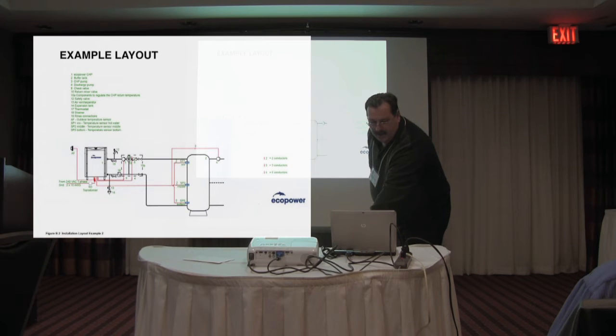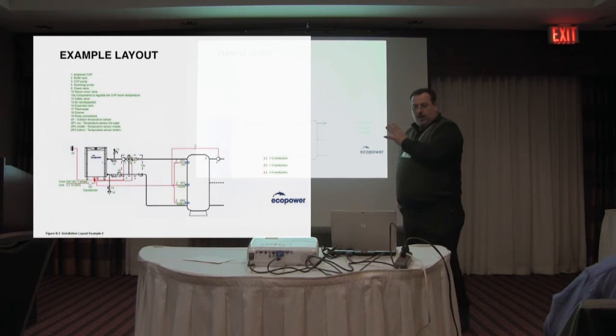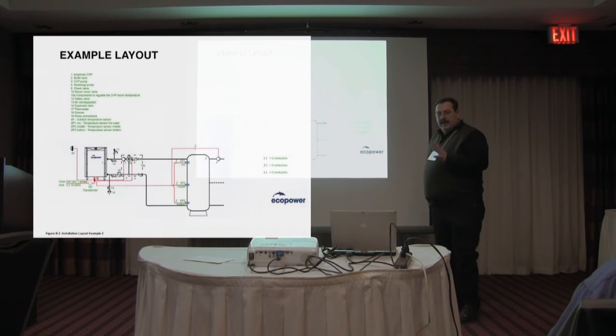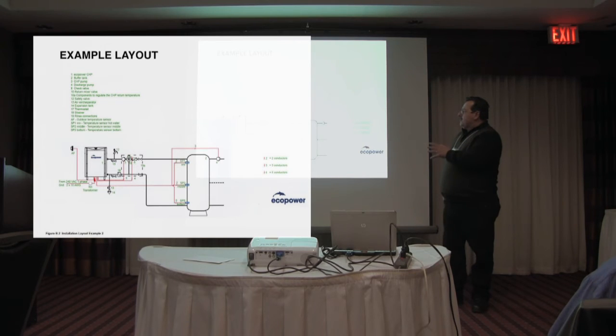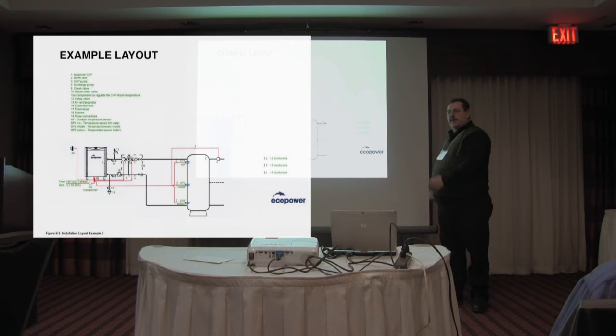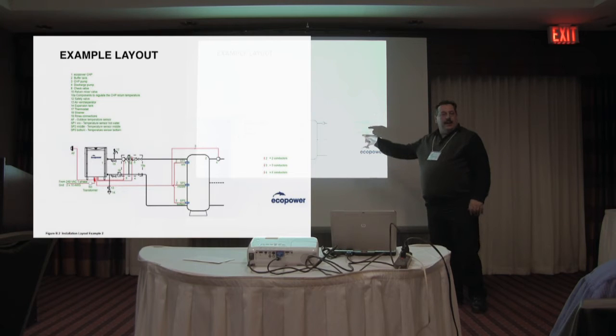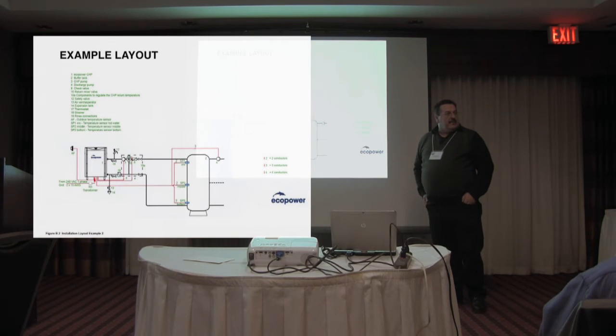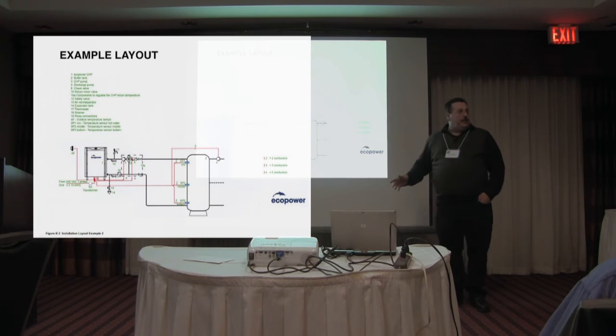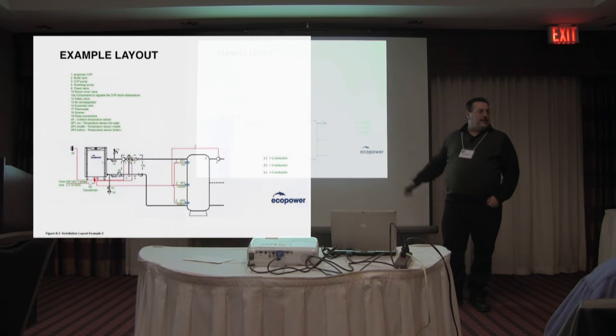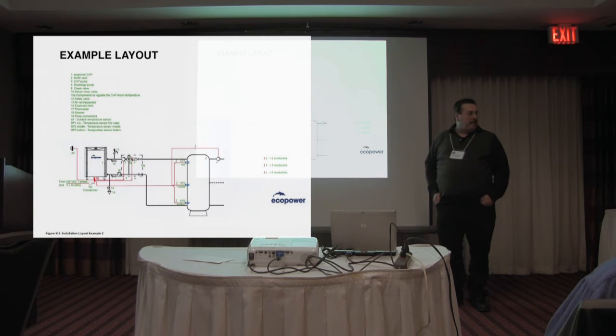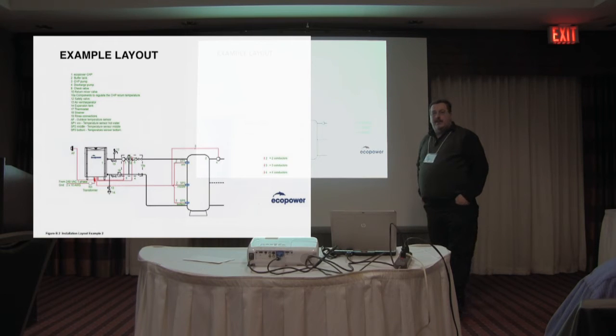So the integration, or this portion of the system, by doing it this way, what you've done is you've mechanically decoupled the CHP from the entire system of the house. All that CHP cares about is the water in that tank and what temperature it's at. So it makes everything downstream of that really simple. Now you can do whatever you want downstream. You can have various flow rates, it doesn't matter. It doesn't affect the CHP. In terms of troubleshooting, it's a lot easier as well.